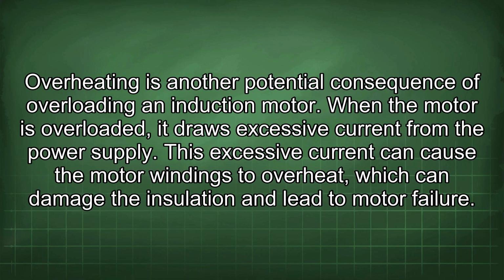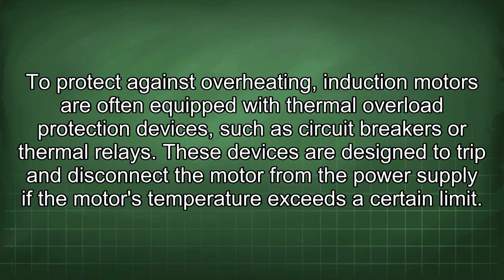Overheating is another potential consequence of overloading an induction motor. When the motor is overloaded, it draws excessive current from the power supply. This excessive current can cause the motor windings to overheat, which can damage the insulation and lead to motor failure. To protect against overheating, induction motors are often equipped with thermal overload protection devices such as circuit breakers or thermal relays. These devices are designed to trip and disconnect the motor from the power supply if the motor's temperature exceeds a certain limit.